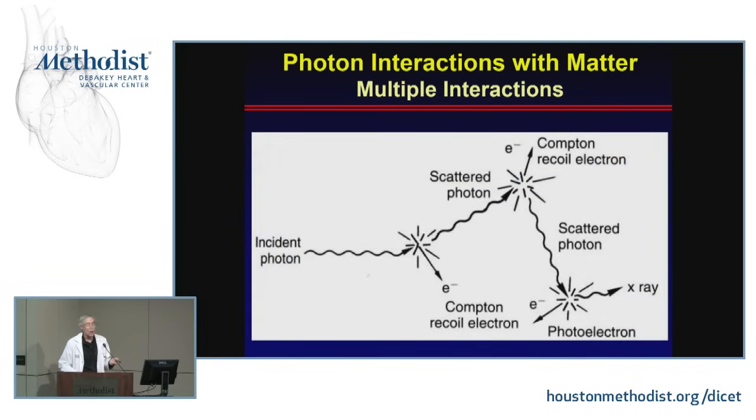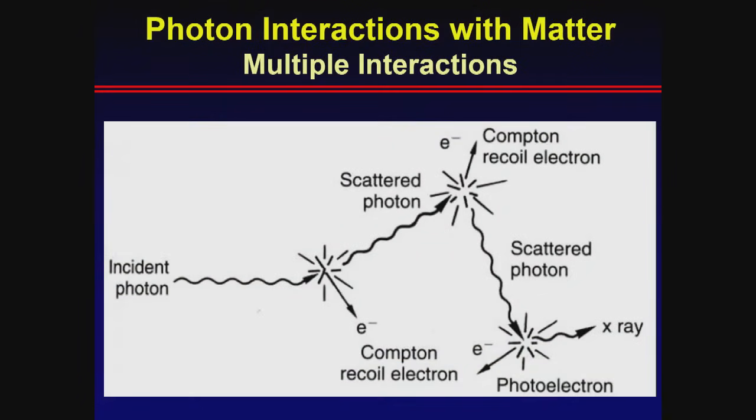The other thing to keep in mind when you think about Compton scattering is that it's just not one thing. I mean, you can have multiple scattered events, okay? So it's like a ping pong ball going through space. It can bump into this and then bump into another one and then bump into another one, and finally, you'll measure all of these until you go outside the energy window. Okay? So this is really bad because you can be out all over the place here in terms of where an event initially occurred and where you finally register it.